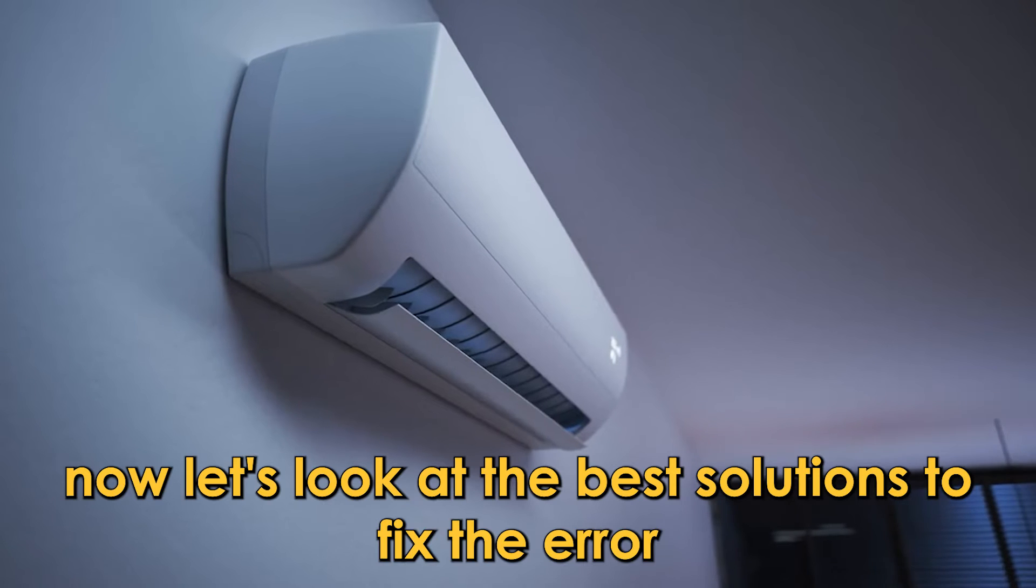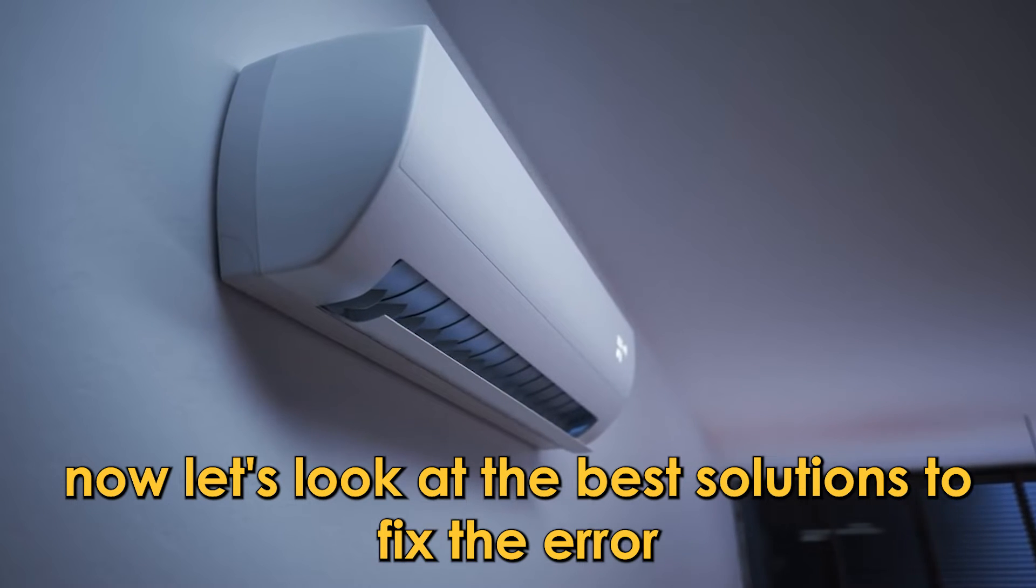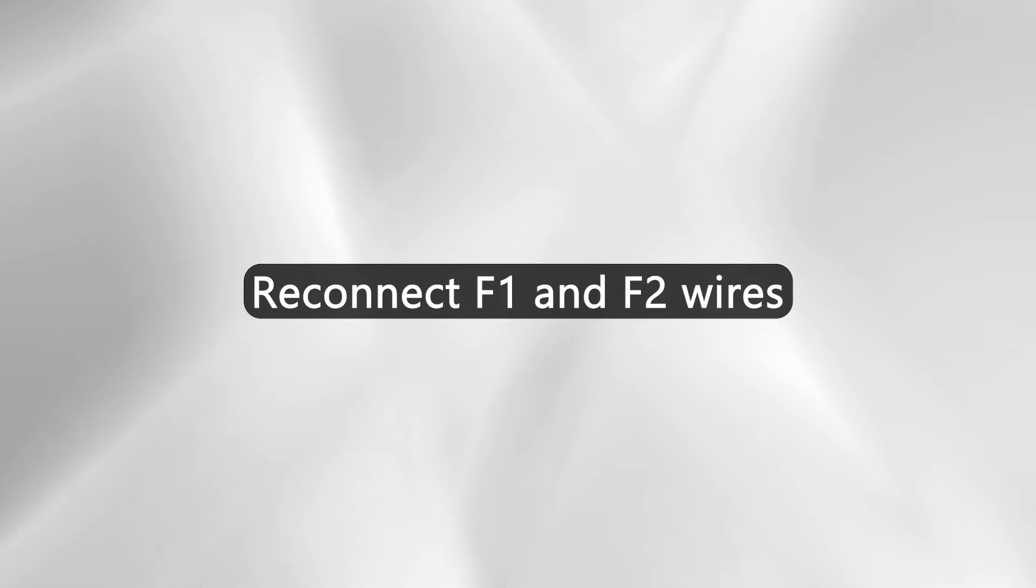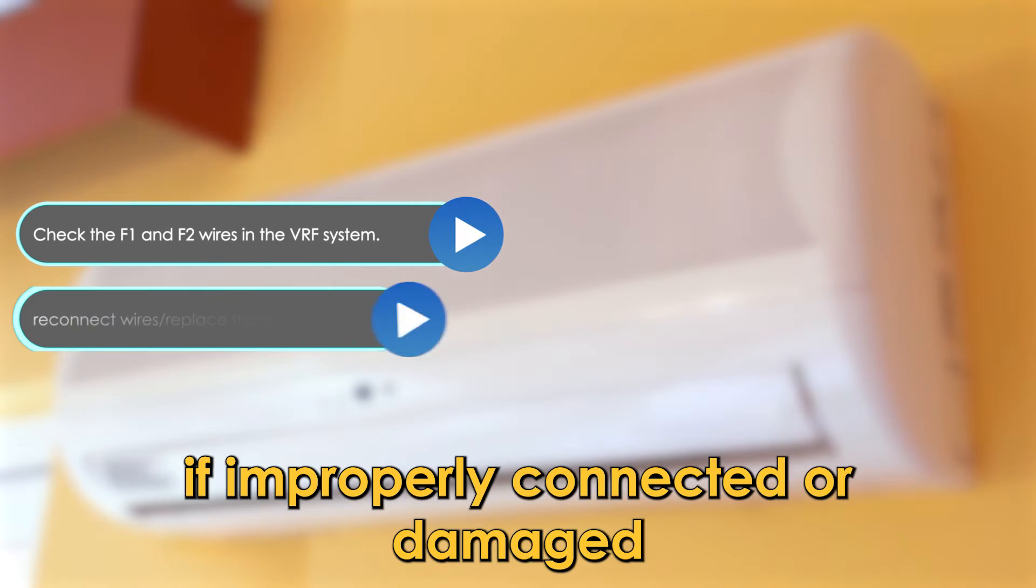Now, let's look at the best solutions to fix the error. Reconnect F1 and F2 wires. Check the F1 and F2 wires in the VRF system. If improperly connected or damaged, reconnect the wires or replace them with professional help.